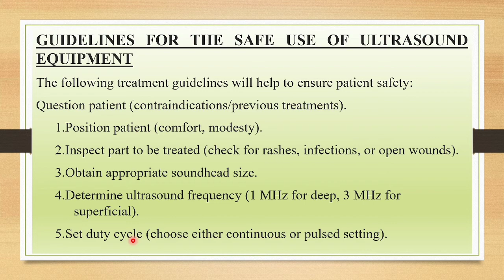And we need to apply the coupling gel to the area, and set the treatment duration. If our goal is to increase tissue temperature, we need to give 5 to 10 minutes. For chronic cases and chronic fracture healing, we can give up to 15 to 20 minutes. Maintain contact between the skin and the applicator, and move at the rate of 4 centimeters per second, for two times the size of the effective radiating area. We need to adjust the intensity to the perception of heat. If it gets too hot, turn down the intensity or move the applicator slightly faster.